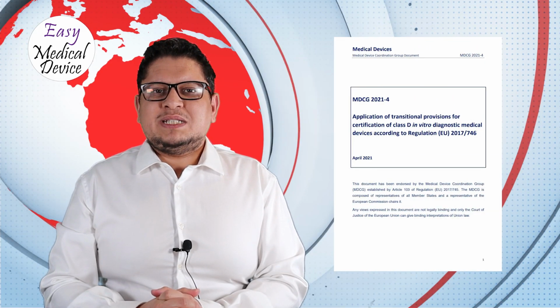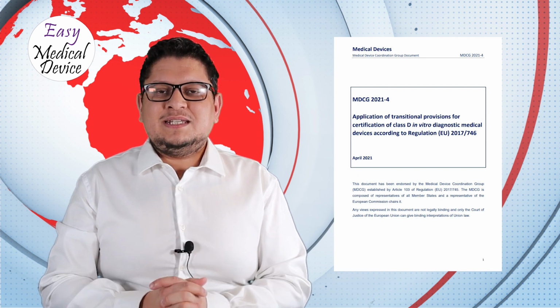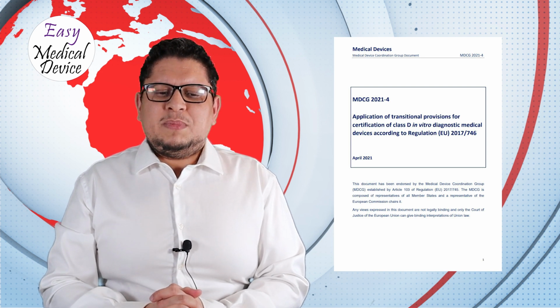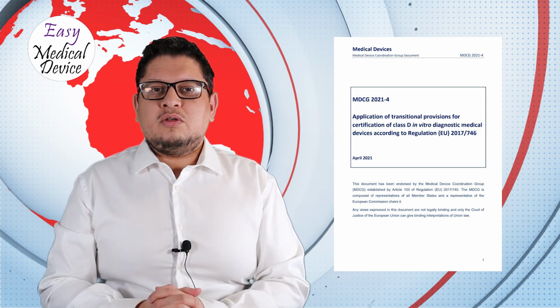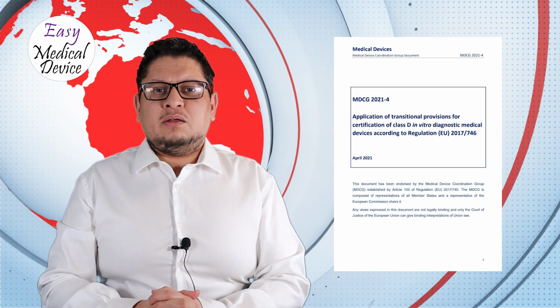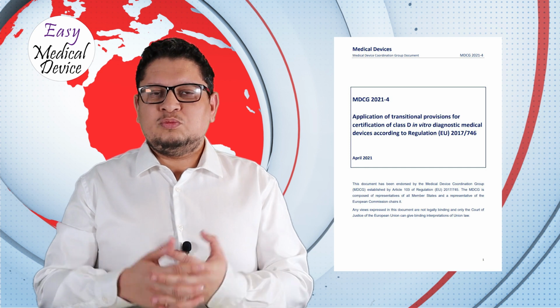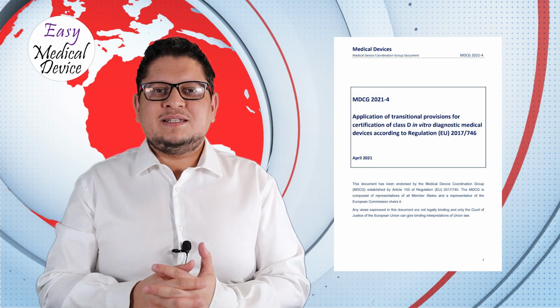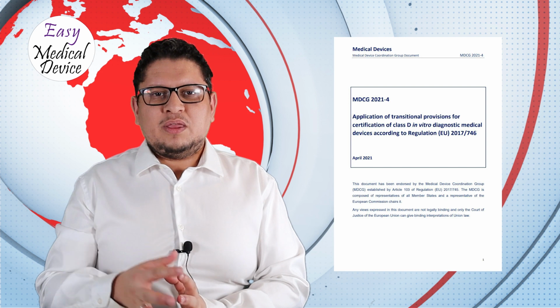Then the next guidance is the MDCG 2021-4, which is the application of the transitional provision for certification of class D in vitro medical devices. So mainly it's for in vitro diagnostics, so 2017-746. Here you have also a lot of questions and answers about class D IVD and how to use that. A question, for example, is about the European Union reference labs. Can we place devices on the market if those European Union reference labs are not designated? Can we place them without the expert panel being designated and available? So these are things that this guidance is answering. So if you have an IVD product class D, then you can go to this guidance and see if there is some question that you are asking yourself, and where the answer is there.